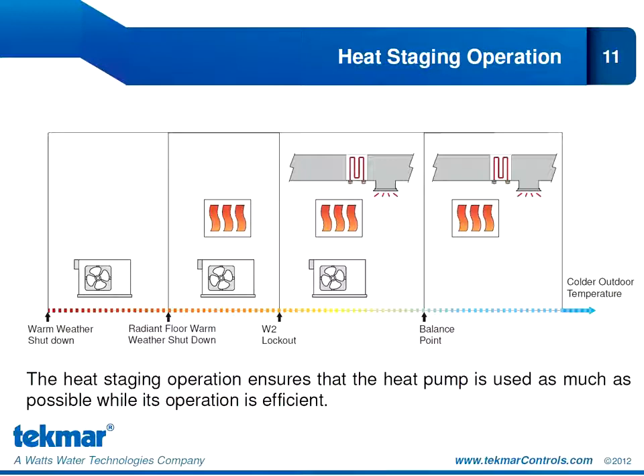The first function we'll go over is the heat staging operation. I'm going to draw your attention to the bottom axis. On this side of the axis, it's represented in red for warm weather. And as we go along, the outdoor temperature is getting increasingly colder until we reach cold outdoor temperatures shown in blue. When we are above the warm weather shutdown, we have no need for heating, so we're not going to stage any of our heating equipment.